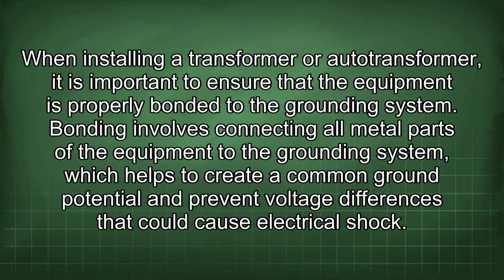When installing a transformer or autotransformer, it is important to ensure that the equipment is properly bonded to the grounding system. Bonding involves connecting all metal parts of the equipment to the grounding system, which helps to create a common ground potential and prevent voltage differences that could cause electrical shock.